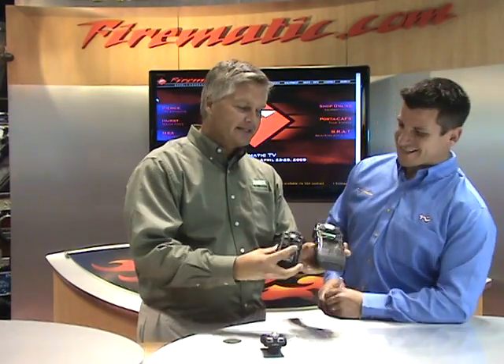We've got another one here — this one is probably not familiar to people. These are diffusion type instruments designed to be personally worn. You can see the difference in size between the two monitors — that difference is because this is a pump-driven instrument. This is the Altair 5. The '5' means you can have up to 5 gases. Pump-driven instruments allow remote sampling — we draw toxic gas, combustible gas, and oxygen-deficient gas toward the instrument through what would typically be a wand.